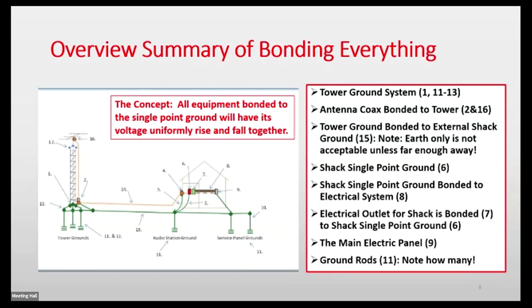Depending on how far your tower is from the house, there's a general rule of give and take around 50 feet. If the tower is more than 50 feet away, you typically don't have to tie those two together - there's enough impedance in that cable that it doesn't provide enough benefit to have that ground connection. In commercial sites, we seldom see compounds big enough that the towers are that far away anyway. You can put it in, it doesn't hurt anything, but you don't always see that connection if the tower is 50 feet or more away from the structure - number 15 isn't necessarily in place in those cases.